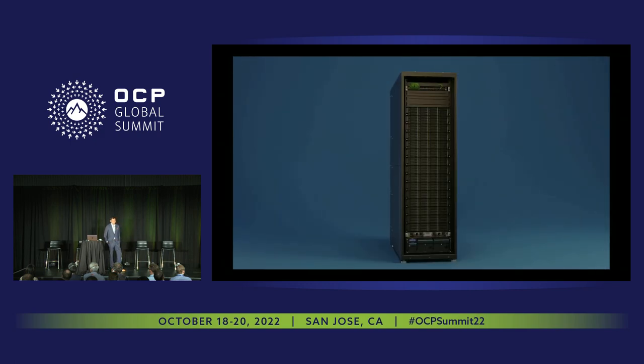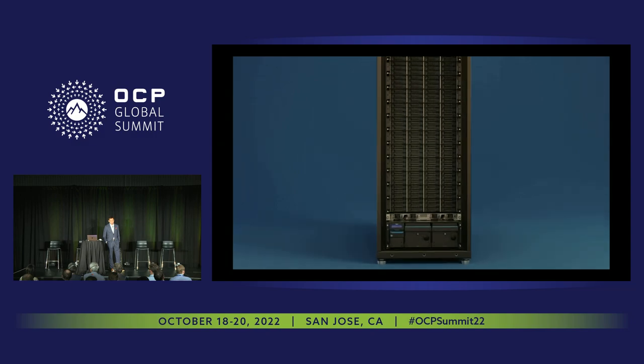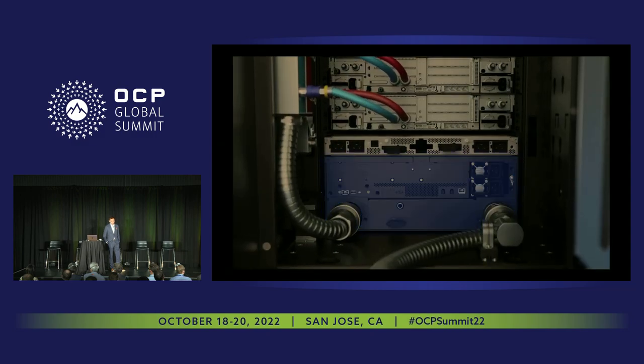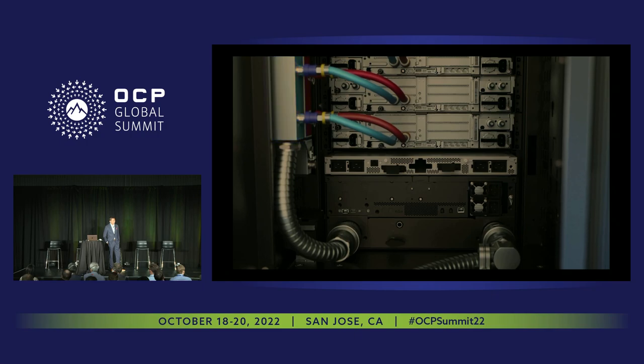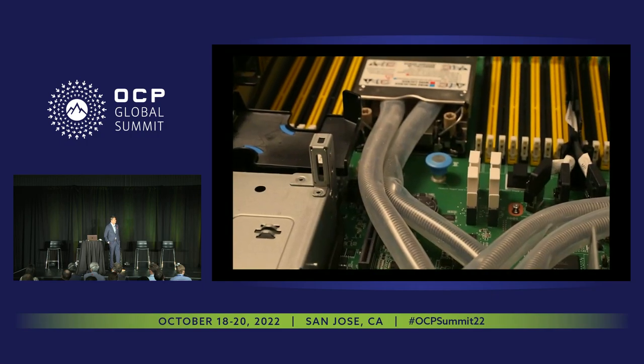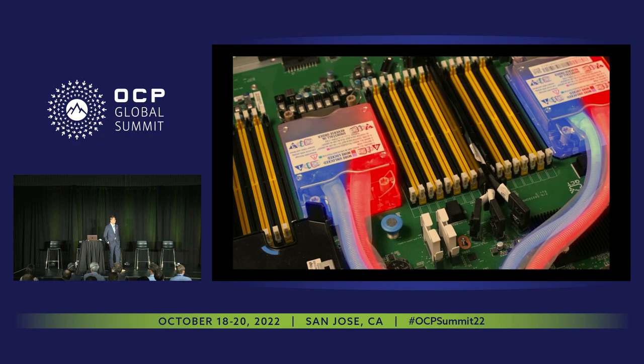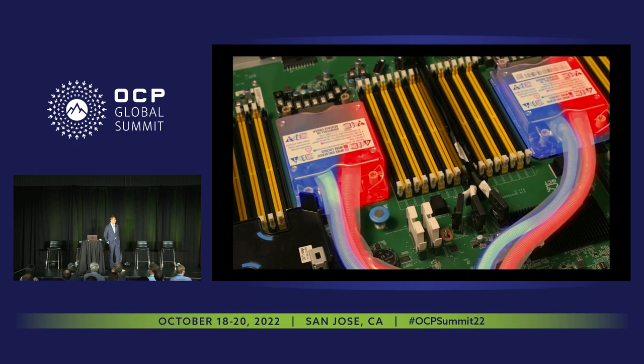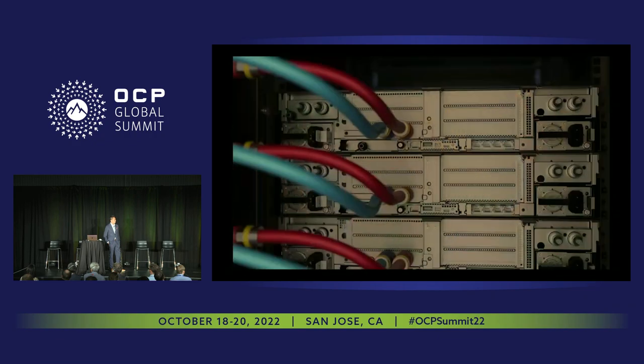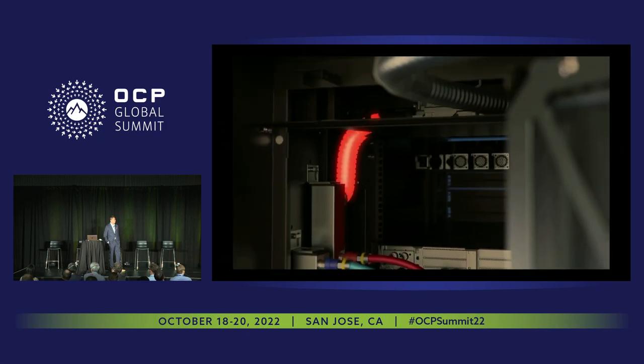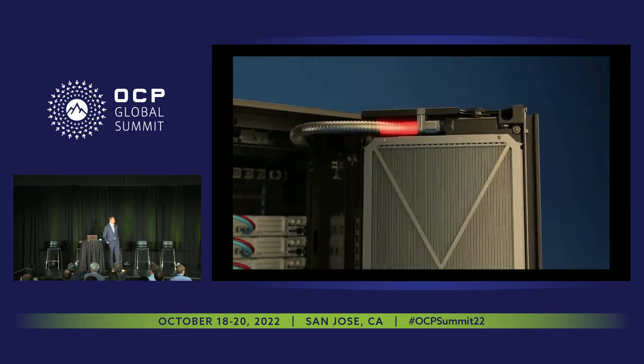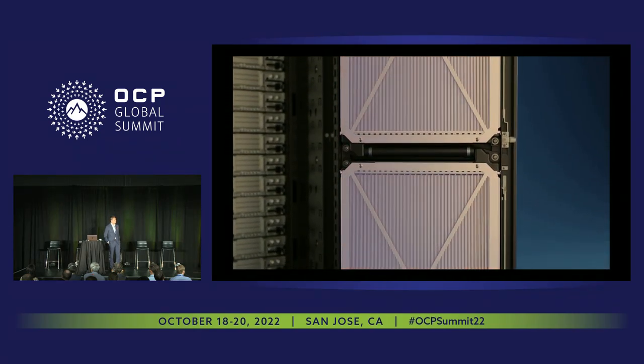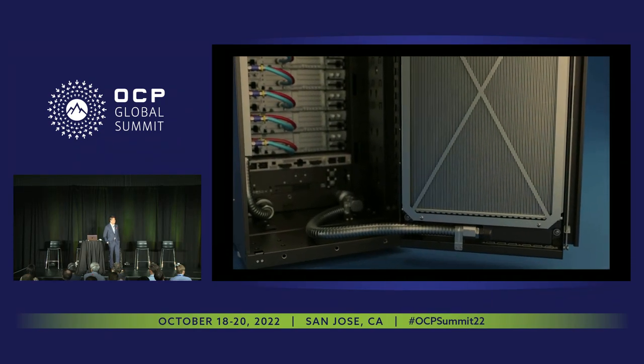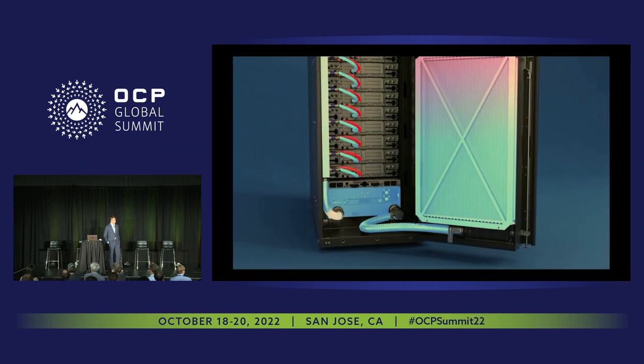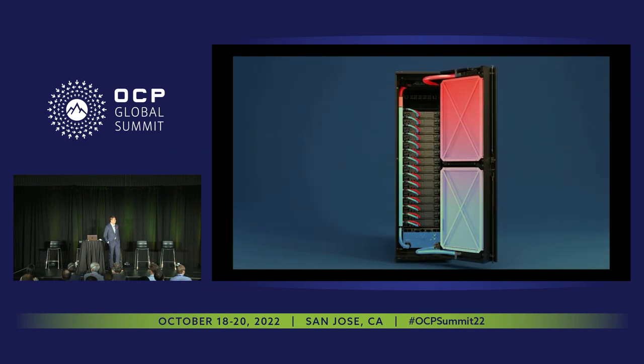QCT's liquid cooling solution starts at the cooling distribution unit, CDU, at the bottom of the rack, which pumps coolant liquid up through the cold manifold that travels around the CPU to cool down each node. The heat from the CPU is drawn to the liquid, which then passes through tube piping to the hot manifold. The hot liquid then travels to the top of the rear door radiators for heat dissipation, and during this process fans draw heat out of the rack. Finally, the heat-exchanged, cooled-down coolant enters back into the CDU to run a new cooling flow cycle.